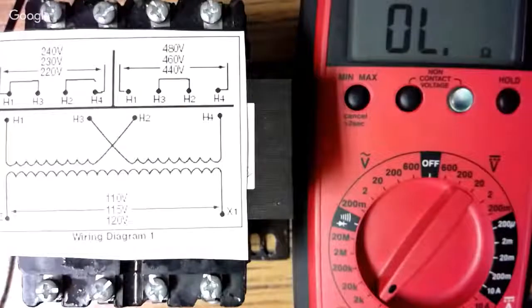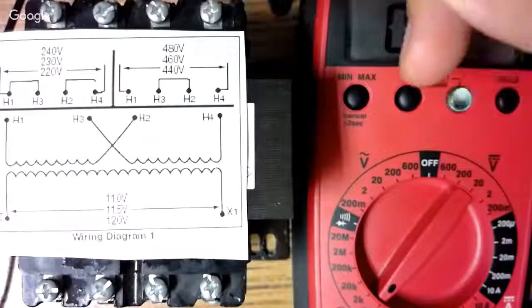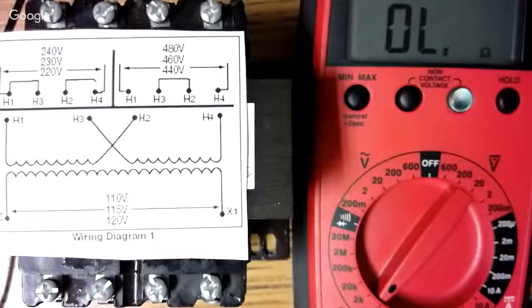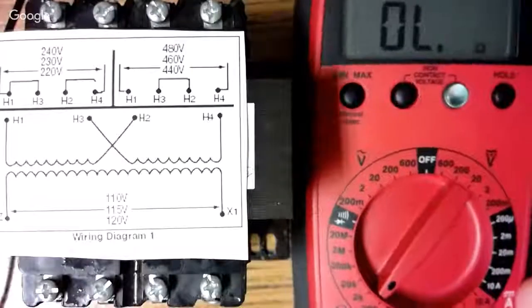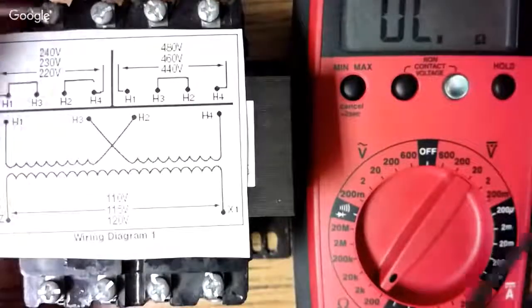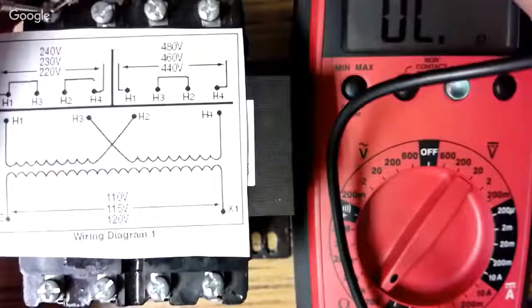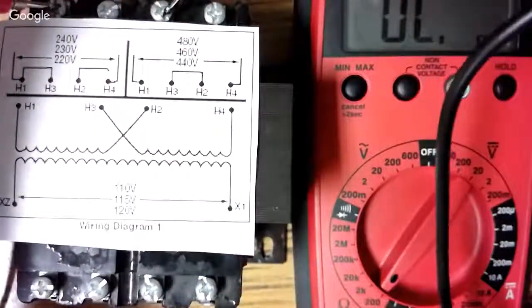Now, on my secondary, the tabs have been removed. Our jumper configurations, you want to always have that. So when in doubt, you can simply take the screw, disconnect the power, lock it out, pull the little tabs off, little metal jumpers here, and test it that way. So we're going to look at one coil here. And so it's showing H1 and H2. So let's check H1, which is here. And let's follow it around to H2, which is the third one.